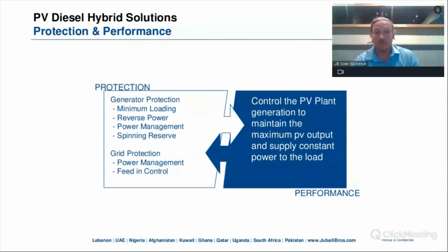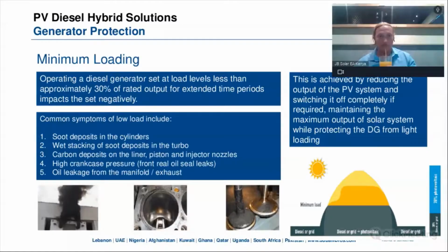But it also protects the grid. Power management, again, that's the reactive power and the active power. And the feed-in control, meaning if you're allowed to send power back to the national grid, it's the fuel save controller that will regulate this. And the performance, as we said, the main performance issue is to maximize the PV consumption and minimize the diesel consumption. So that is also the job of the fuel save controller.